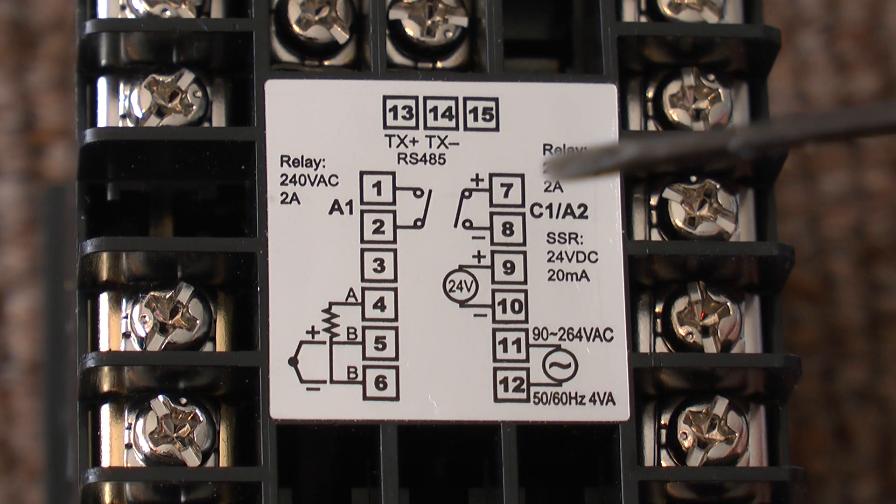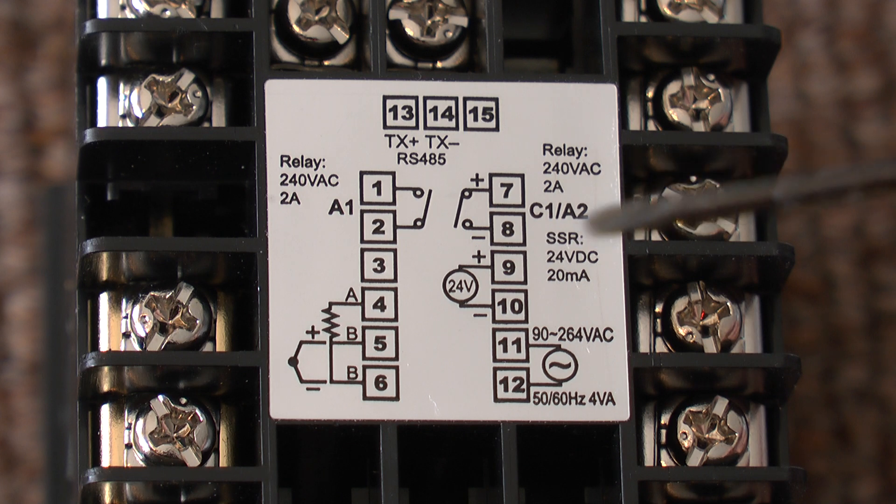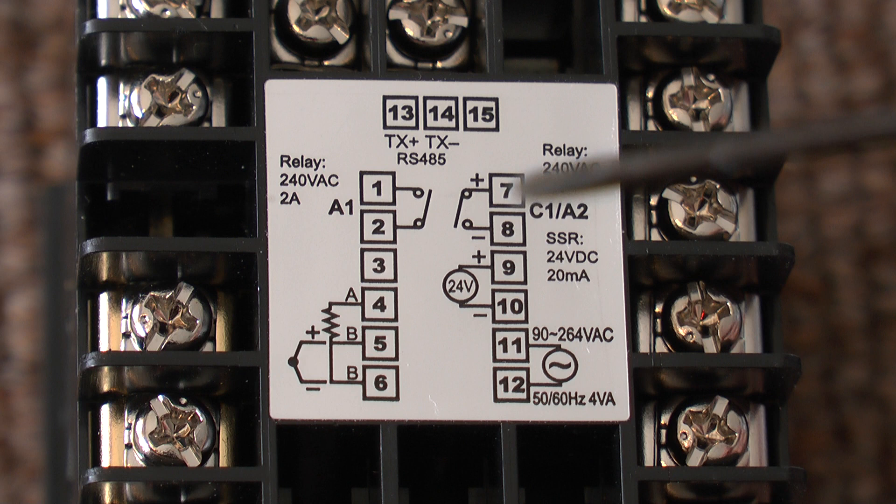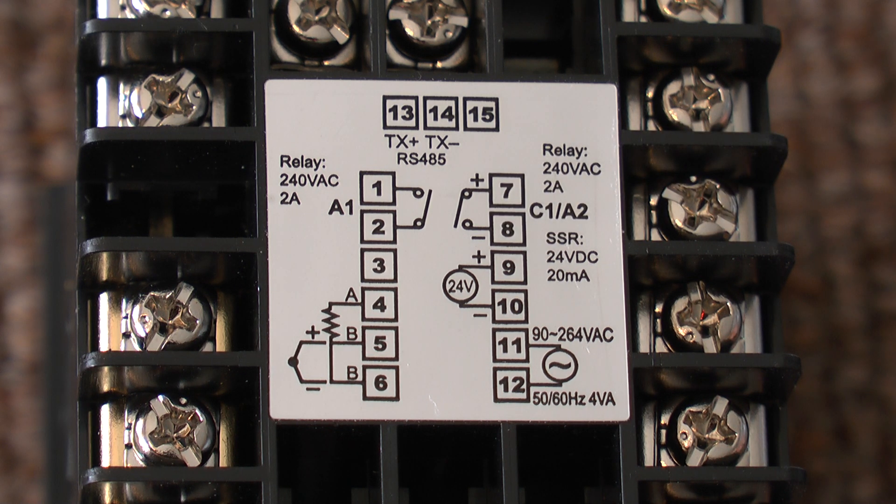The output for this controller gets connected to terminals 7 and 8. This particular one is a relay output controller and therefore between terminals 7 and 8 you simply have a switch that can be used to turn on a contactor or relay.